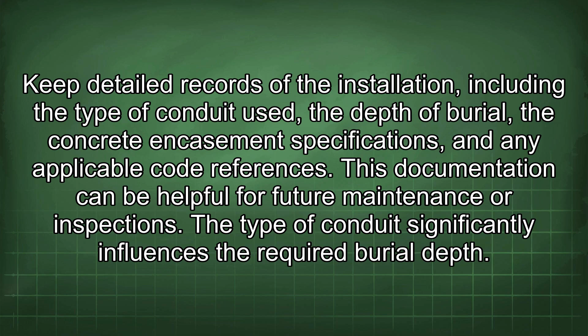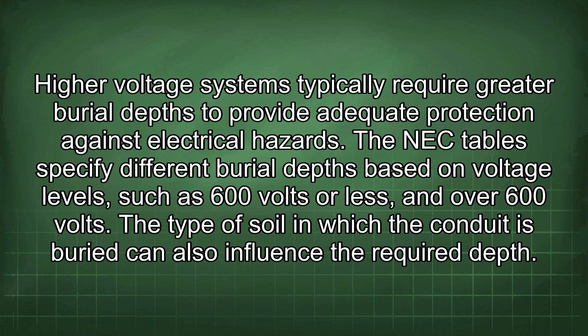The voltage of the conductors within the conduit also affects the burial depth requirements. Higher voltage systems typically require greater burial depths to provide adequate protection against electrical hazards. The NEC tables specify different burial depths based on voltage levels, such as 600 volts or less, and over 600 volts. The type of soil in which the conduit is buried can also influence the required depth. In areas with rocky or abrasive soil, a deeper burial depth may be necessary to protect the conduit from damage. Similarly, in areas subject to freezing temperatures, a deeper burial depth may be needed to prevent damage from frost heave.